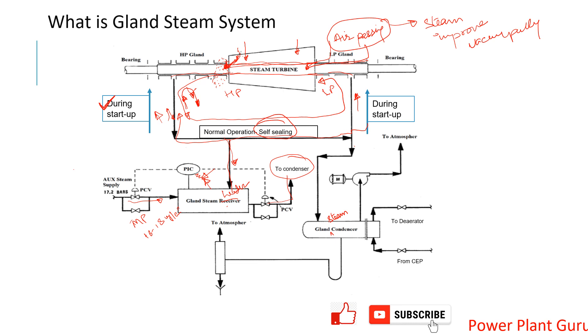The CEP water which is pulling water from condensate, that will pass through this gland steam condenser. Then it can be routed to condenser as well. Whatever steam it is utilizing, the CEP water will gain that heat from this hot steam and that will go to deaerator as hot water. Hot means whatever the heat gain, delta T it gains. CEP water goes from gland steam condenser outlet. That is the way to utilize that heat and water is recovered and put to condenser as well.